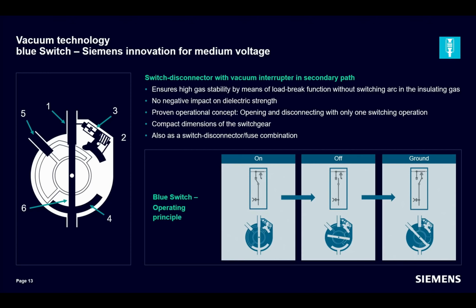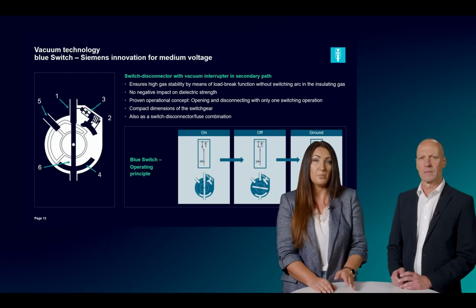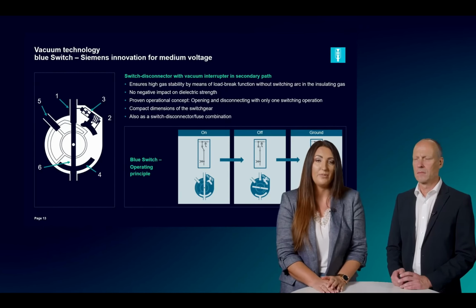On the pictures on the right-hand side, you will see the 3 switching positions, which are selectable by a pair of switching blades. The switching position on transmits the current from the busbar to the cable feeder or vice versa, which is therefore called the main path. In switch position off, the current flow is interrupted and the disconnecting function is fulfilled. Hereby, a safe isolating distance is provided by a gas-insulated contact gap and not across the vacuum interrupter. The switch position earth then safely grounds the cable feeder.